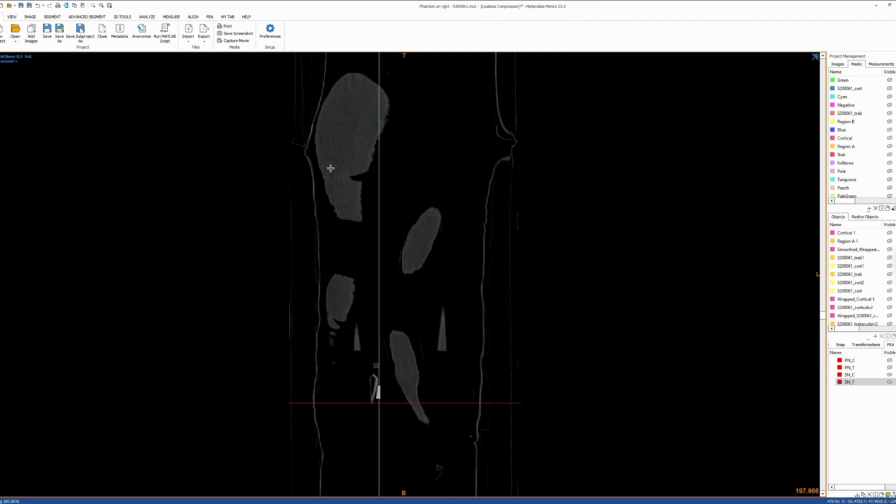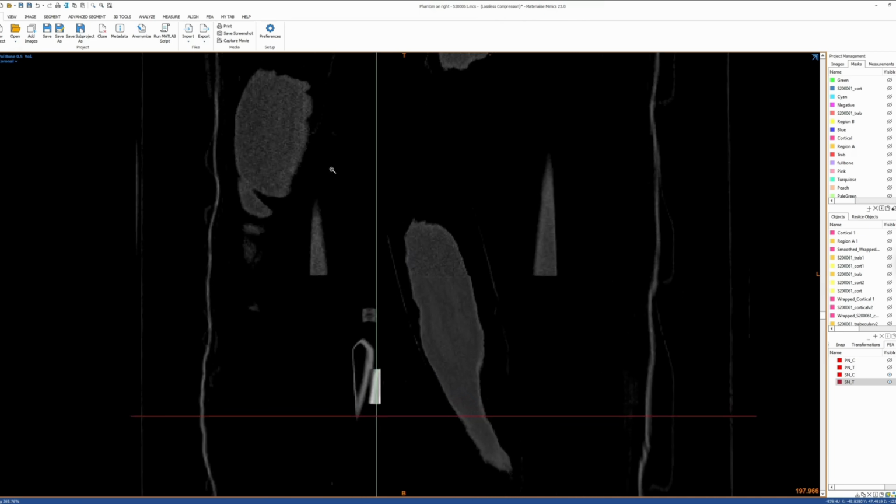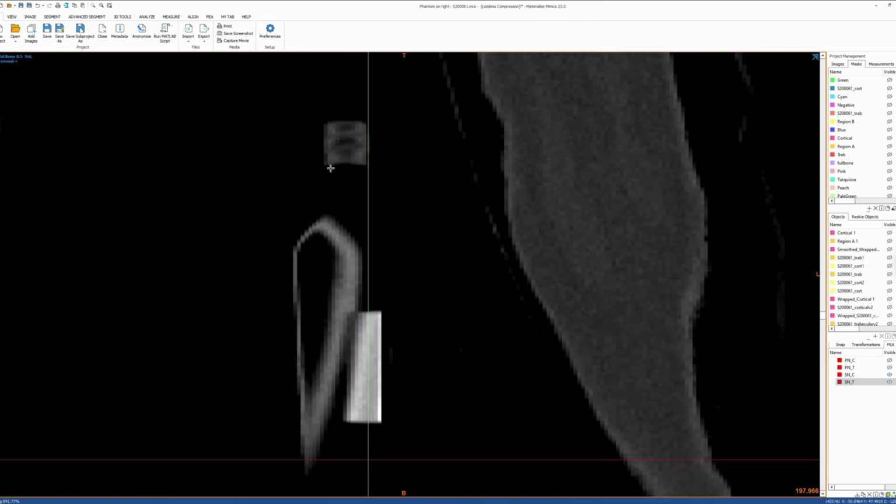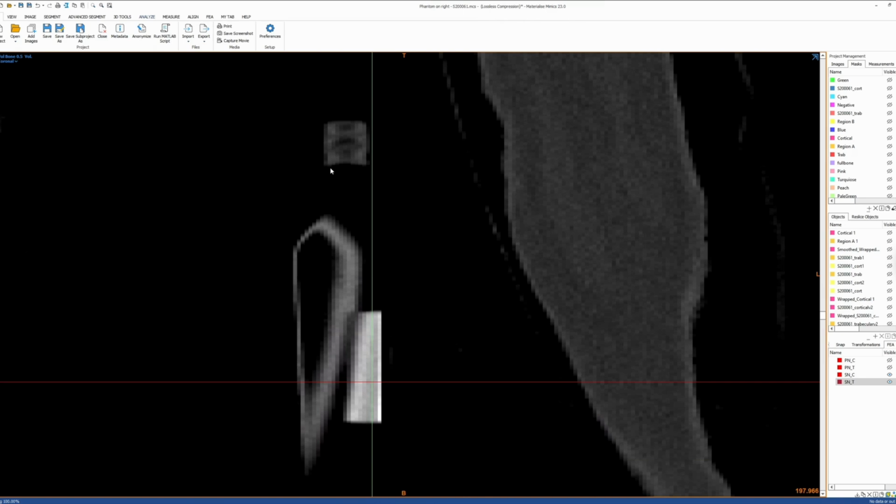Here, we're going to use our CT phantoms to identify what Hounsfield unit is associated with what calibrated density. For our lab, we use a SB3 cortical bone block and a bottle of water for this purpose.